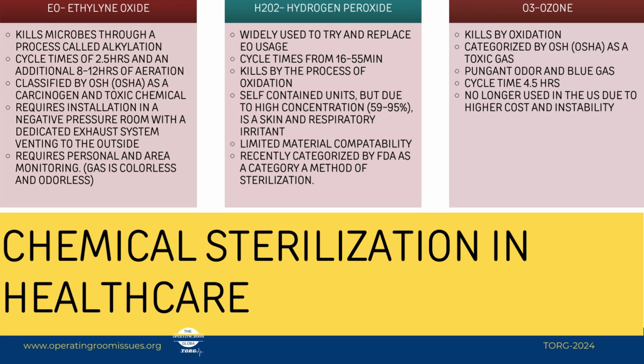So, chemical sterilization choices in healthcare: ethylene oxide, hydrogen peroxide, and ozone technology, which is no longer used in the United States because of cost and because of the actual danger it poses. As a matter of fact, at the time of this conference, hydrogen peroxide has become the number one chemical sterilization choice for the United States, with a new cycle that was released to be able to do flexible endoscopes.